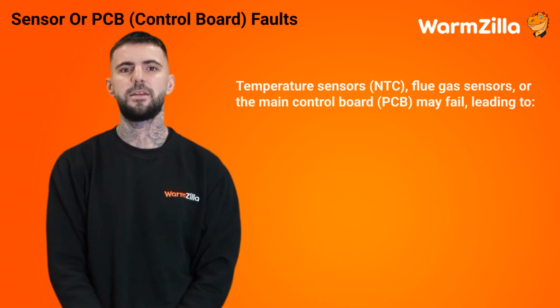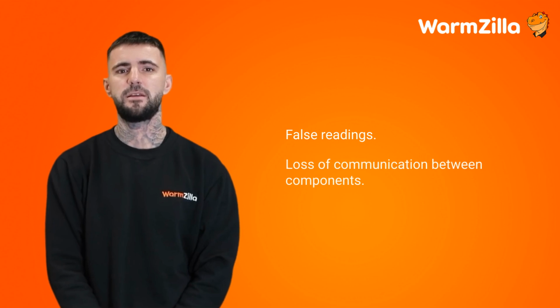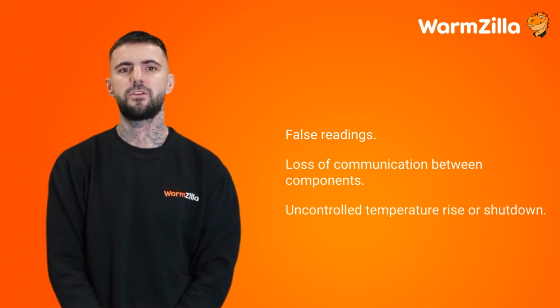Sensor or PCB control board faults. Temperature sensors, NTC, flue gas sensors, or the main control board, PCB, may fail, leading to false readings, loss of communication between components, uncontrolled temperature rise or shutdown.